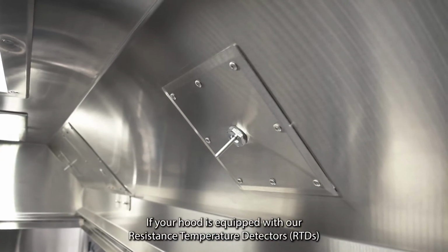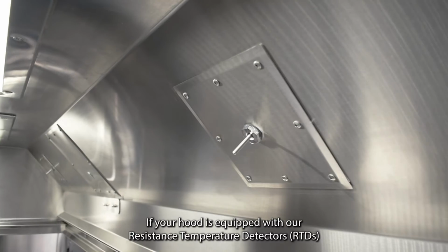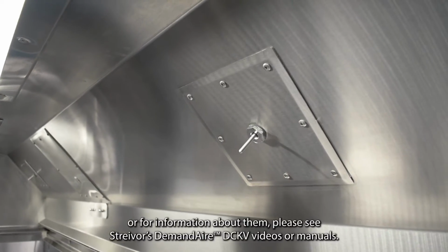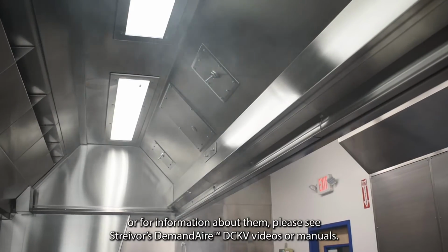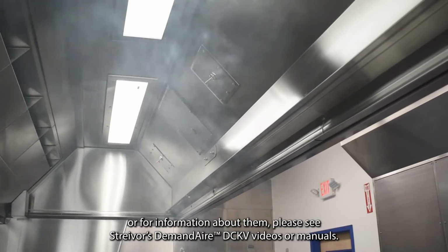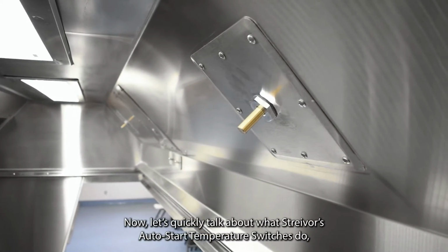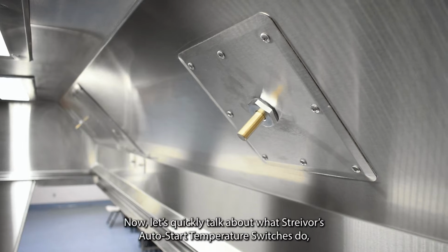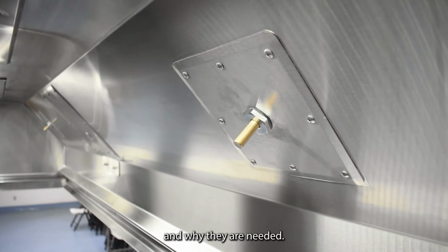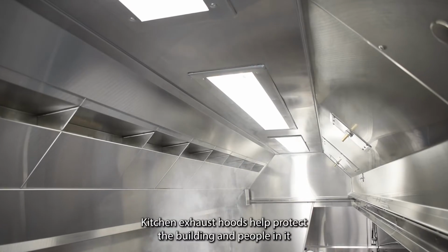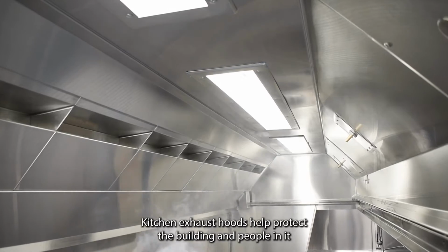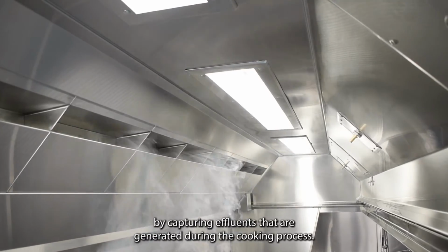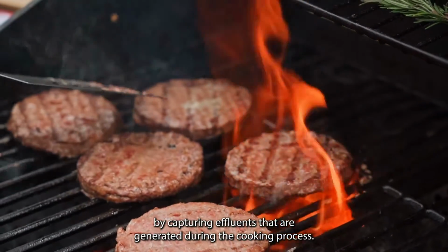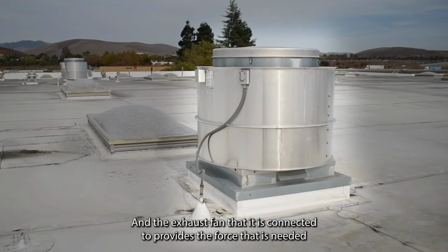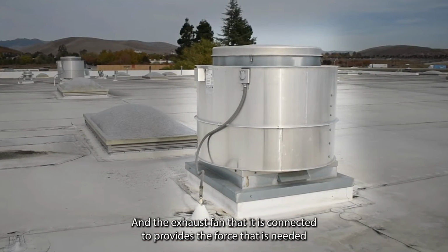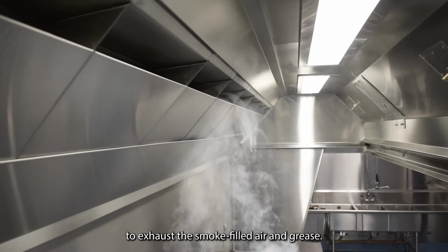If your hood is equipped with our resistance temperature detectors, RTD, or for information about them, please see Streivor's DemandAire DCKV videos or manuals. Now, let's quickly talk about what Streivor's Auto Start temperature switches do, and why they are needed. Kitchen exhaust hoods help protect the building and the people in it by capturing effluents that are generated during the cooking process. And the exhaust fan that it is connected to provides the force that is needed to exhaust the smoke-filled air and grease.